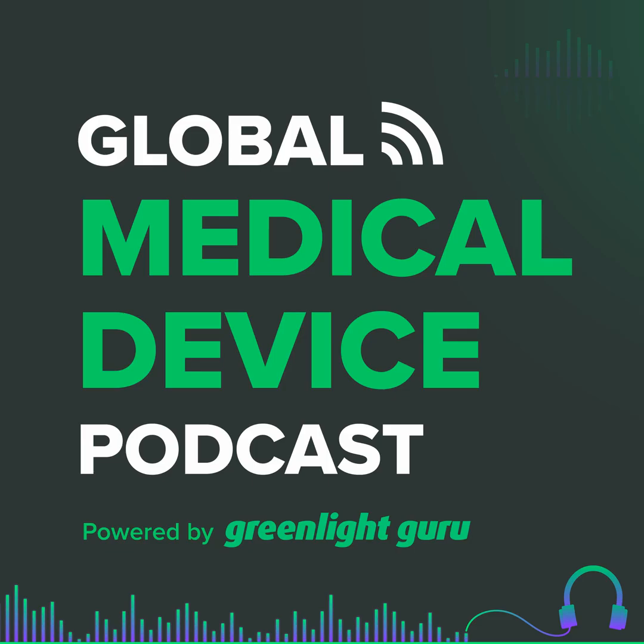Here's a quick example, Eddie, from a customer that I'm working with right now. Remember, I said before, the recent guidance expands this to the entire medical device universe, including in vitro diagnostics. So right now, my customer and I are having a discussion slash debate, if you will, because we want to use the PCCP to pre-validate some additional labs that can do the analysis for this particular in vitro diagnostic sample. Based on my reading of the regulation or the guidance, I don't see any reason why we should not be able to use the PCCP to do that.